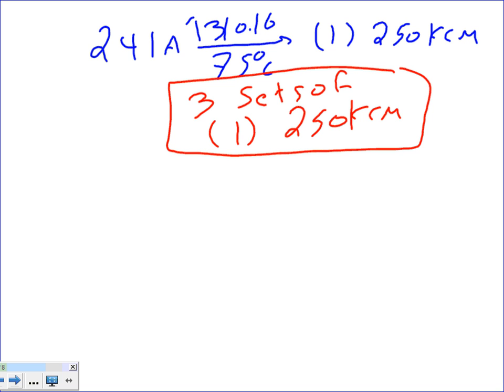Any questions, guys, about this? So basically, we're going to end up with 3 sets. Each set will have 2 conductors, 350, and 1 set with 1 conductor, 250. 1 conductor, 250, the neutral. Now the neutral. Ryan, my friend, you say, Chad, I want to make them all 350 and call it a day. Be it. But there's a big difference in price between 250 and 350. Look at that, 3 sets.